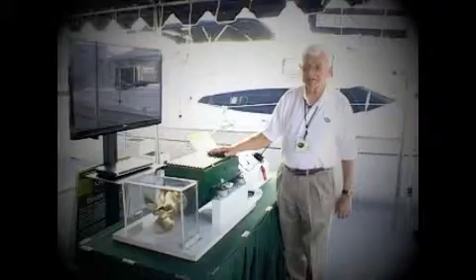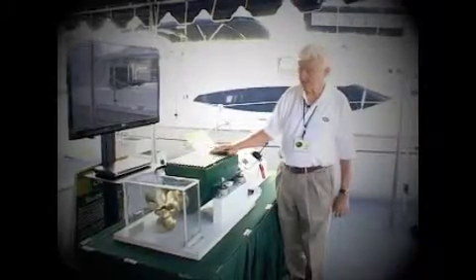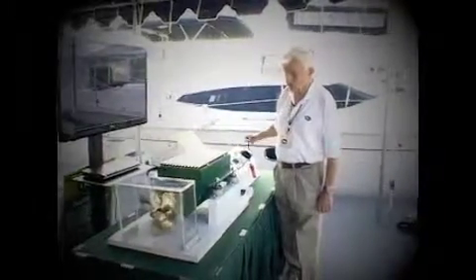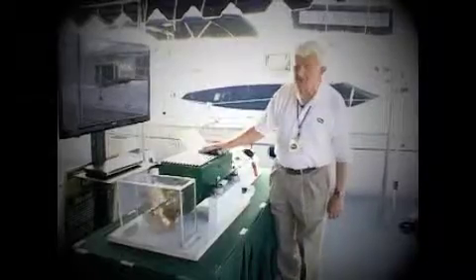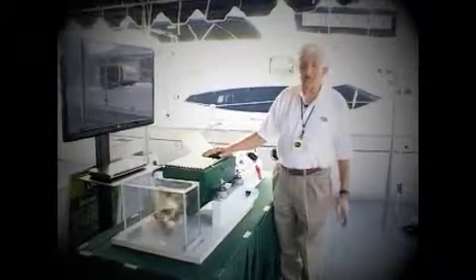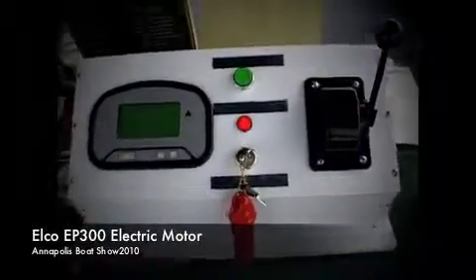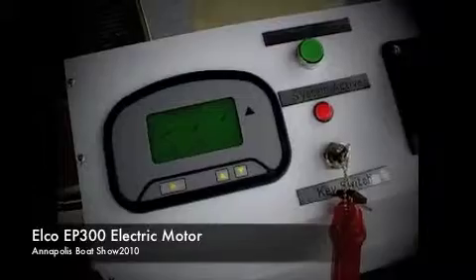The consequences of going with AC is that it's quieter, absolutely quiet. I can run this up and you can't hear a sound from this. With the DC motors, they had to be ventilated and consequently you always heard a whine or a squeaking noise from the motor and the motors could become contaminated.